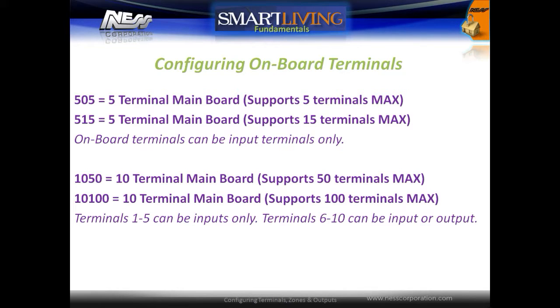The terminals on the 505 and 515 panels can be configured as inputs only. The 1050 and 10100 panels have 10 terminals on board, with the 1050 expandable up to 50 terminals and the 10100 expandable up to 100 terminals. Terminals 1 through 5 can be configured as inputs only, but terminals 6 through 10 can also be configured as outputs.